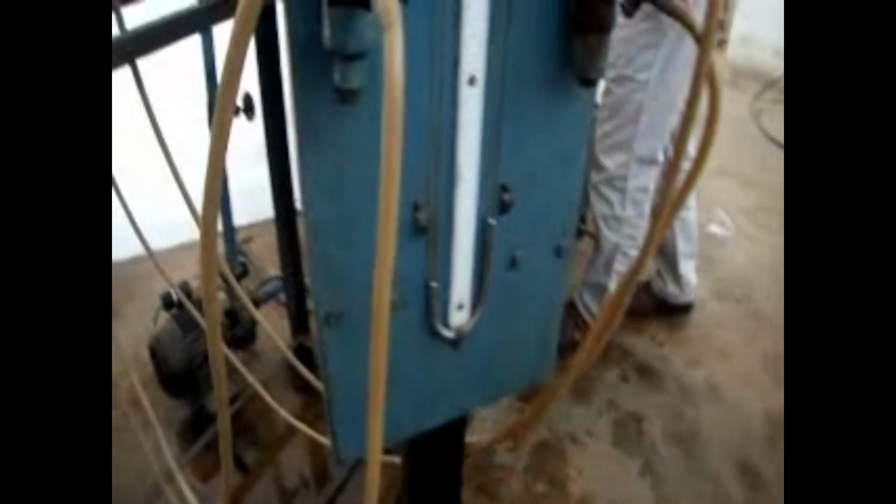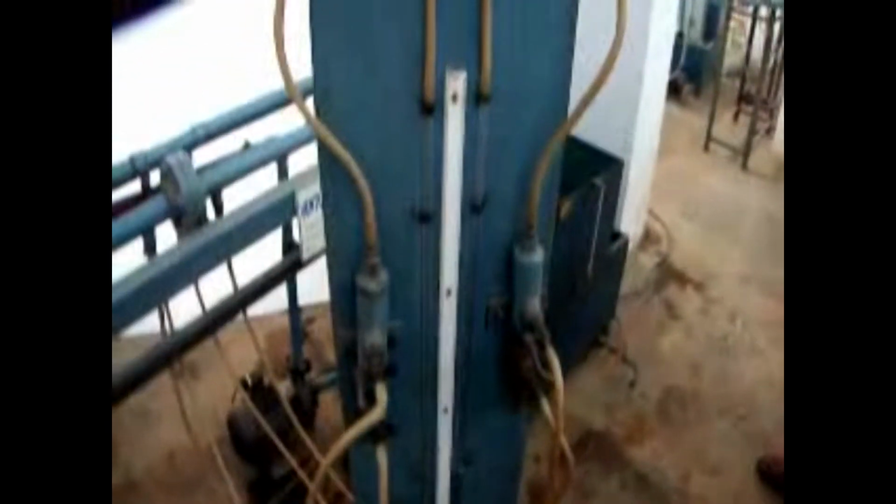So now you can see we have changed the discharge condition. So now this is the second head condition. At the supply side it is 4.3 and discharge side it is 7.8. So 4.3 is supply side and 7.8 is discharge side. So that is the head difference in the second discharge condition.